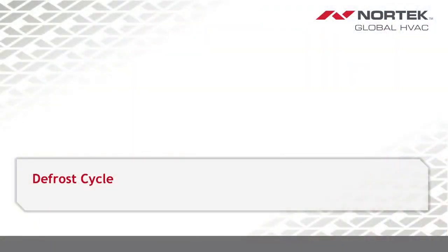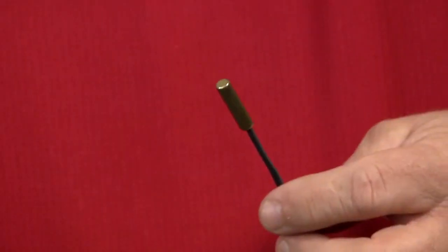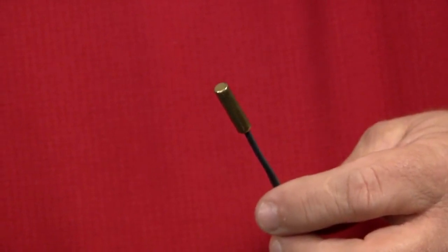All right, so the next thing we want to talk about is defrost, and make sure defrost is functioning. Most of your defrost boards now are using thermistors. So you're going to have an ambient thermistor, such as the one I have in my hand, and you're also going to have a coil temperature sensor on the coil itself. The easy way to explain it is, the defrost board is looking for a differential between the coil temperature and the ambient temperature so that it can sense when it has a frosted coil, and puts it in defrost only when the coil is frosted, so we don't have unnecessary defrost. So checking defrost on a maintenance check, first thing I would do is run the unit in heating mode for a while.